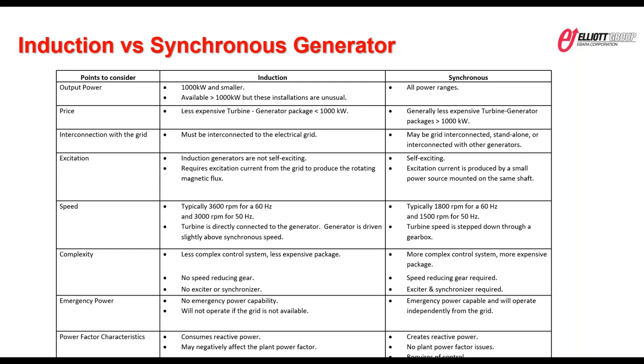So we were talking about the steam side of things and the process piping side of things. Now, what about electrically? When you're talking about a turbine generator, the two main types of generators that exist are induction or synchronous. And really to highlight here, this is kind of a busy slide, but when you're talking about installing a turbine generator, one of the main things you want to ask yourself is, do I want this unit to stay running in island mode if the grid goes down? If the answer is yes, then you have to go with a synchronous generator. It has the ability with its own self-exciter to stay running, or at least, if you have steam, then the turbine can remain running as the steam's available.